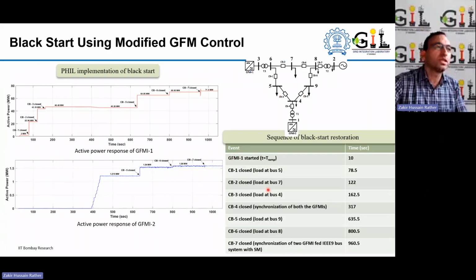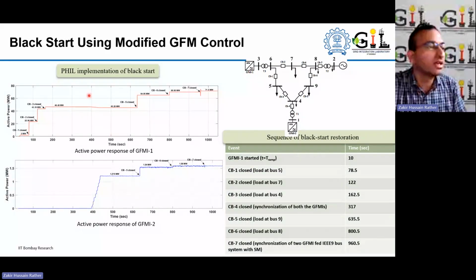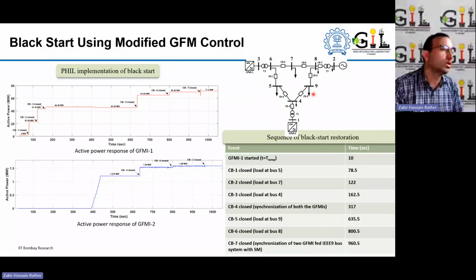So here is the sequence of the black start we conducted in this study, starting from here with this grid forming 1 inverter, which is connected here. It starts with this, and then at different intervals of time, we are charging the line, switching on the respective circuit breakers. And then you can see here grid forming 2 is being connected, which is power hardware in loop. Then again the circuit breakers are switched in sequentially in order to energize the whole system. As a result, with this sequence of switching, we were able to black start this small test system in the lab.